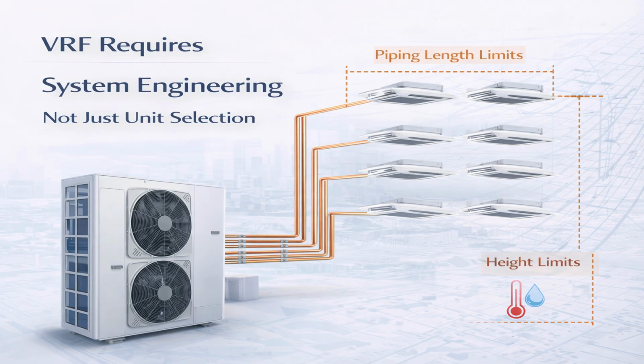Outdoor unit capacity must be correctly matched to the connected indoor units. Indoor unit combination and diversity ratios must remain within allowable limits. Piping lengths and equivalent lengths directly affect refrigerant flow and capacity. Vertical height differences introduce additional pressure and oil return challenges. Each of these factors influences how efficiently refrigerant is distributed across the system.